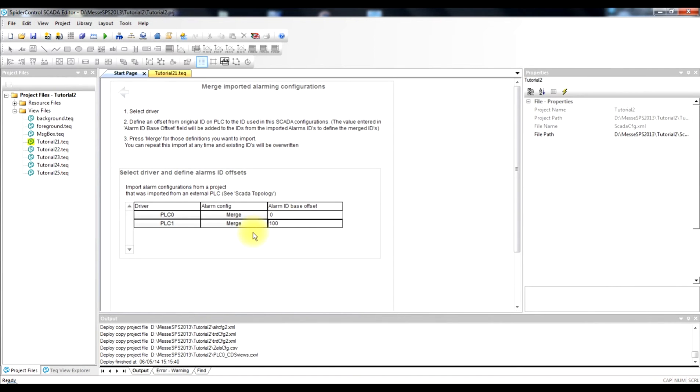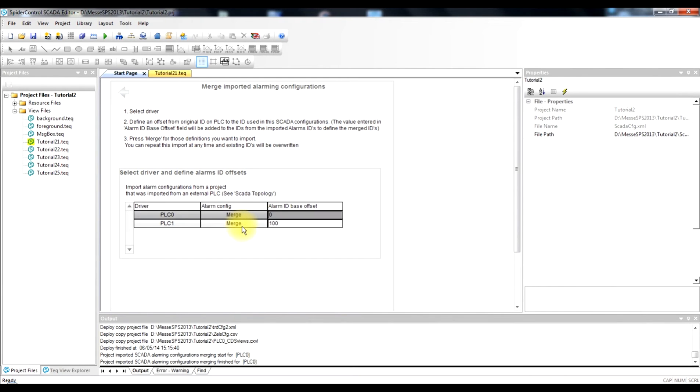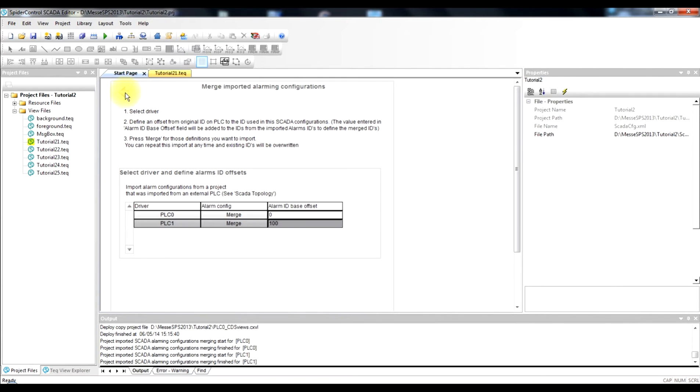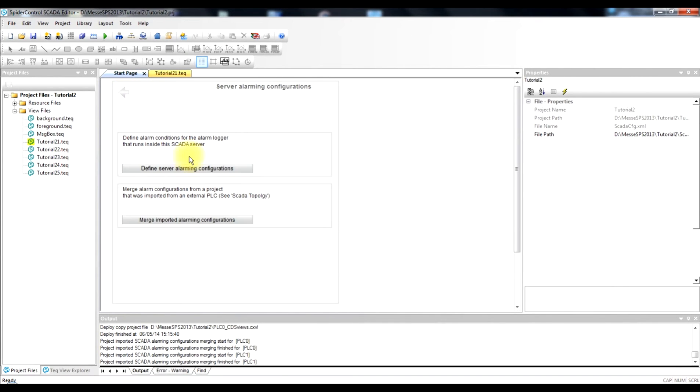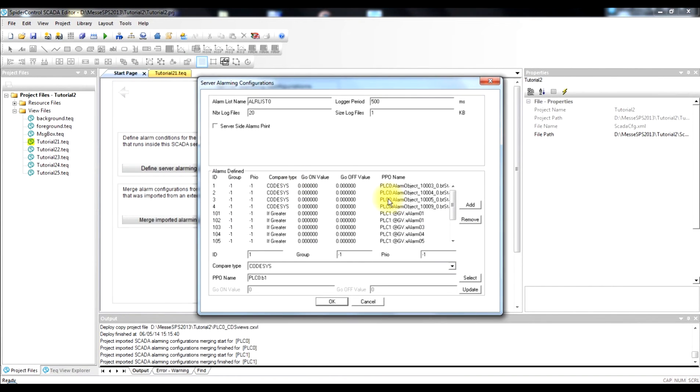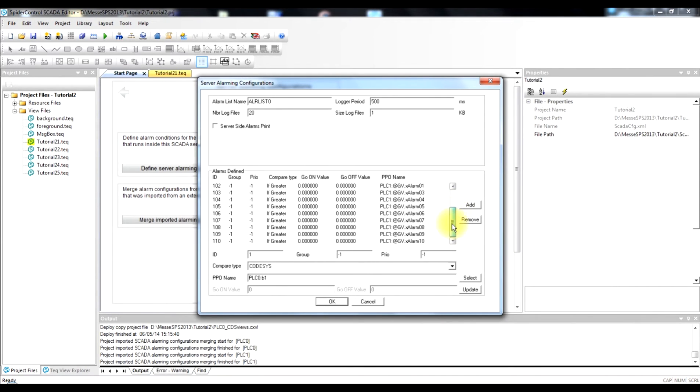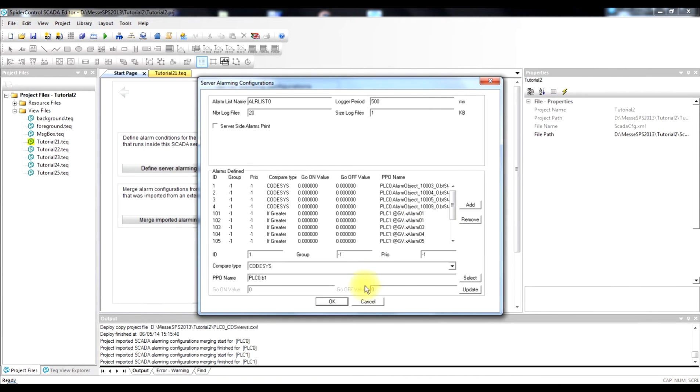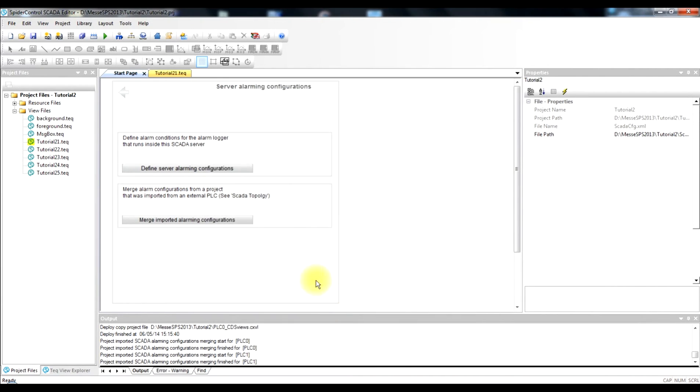So the second PLC will start with an offset of 100. And we will now import the first alarm configuration from the WAGO PLC just by pressing the merge button. We do the same for the second PLC and if we now go back to the overview of all defined alarms we see that we have now automatically generated a valid working configuration.